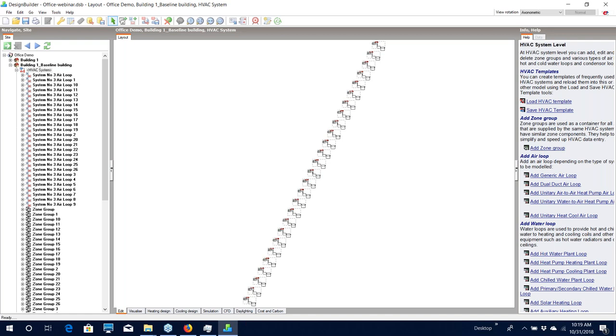If you've already created your baseline building and as your project goes on there need to be changes to the proposed building geometry, internal gains, or schedules, it is necessary to regenerate your baseline building. The best approach for doing this is to delete the existing baseline building and create a new baseline building and HVAC system using the wizards. This is usually a faster process than trying to edit the baseline building to match the edits that you've made in your proposed building.